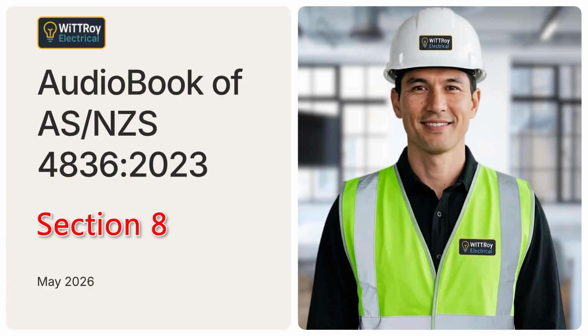Clause 8.4.2. Use of electrically conductive ladders. Clause 8.4.2 explains the use of ladders near electrical installations or equipment. Non-conductive ladders must be used when working on or near electrical installations or equipment. A conductive ladder can create a path for current. This can increase the risk of electric shock or electrocution if the ladder contacts live parts or if the worker bridges between the ladder and electrical equipment.